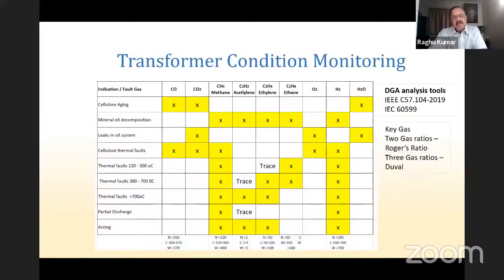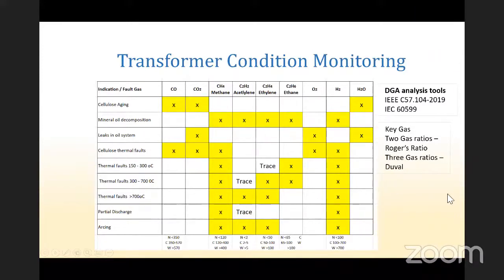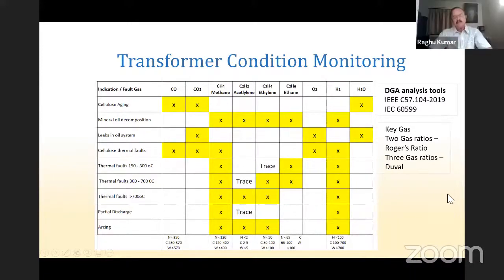And DGA gives out different gases, and it is very difficult to say what the fault is from the gases alone. If you look here, you can see hydrogen is present in most of the faults, and similarly, methane is present everywhere. So the answer to what the fault is, you have to get from an expert. And there are certain software tools which can give you the results.